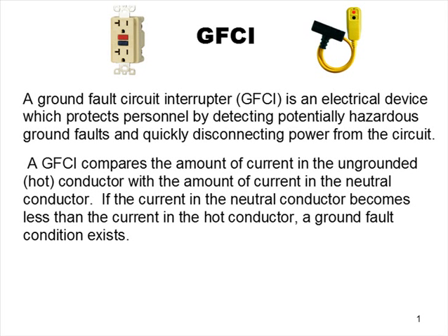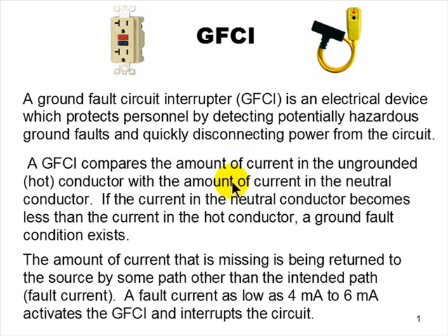So if we just compare the hot to neutral, then we know that we have a ground fault. And anytime current flows to ground, it's a fault. It's not a good thing. Something went wrong, and now we're faulting that current flow. The amount of current that is missing is being returned to the source or to the earth by some path other than the intended path, the fault current. A fault current as low as 4 milliamps, that's 4/1000ths of an amp, to 6/1000ths of an amp activates the GFCI and interrupts the circuit.